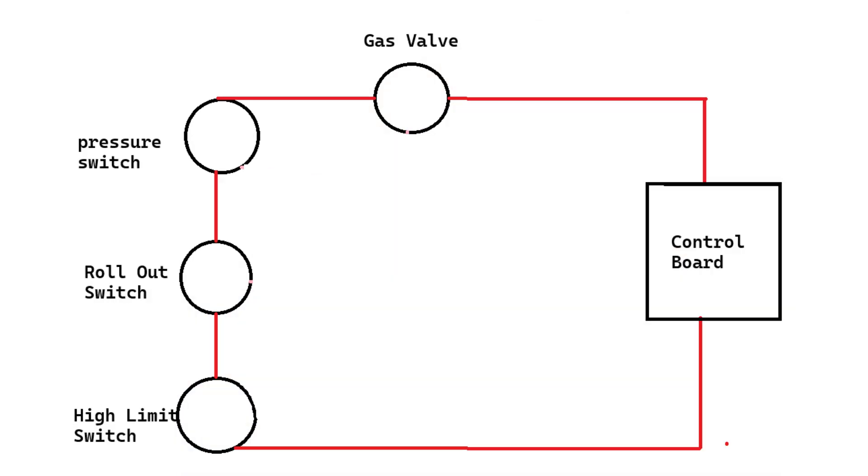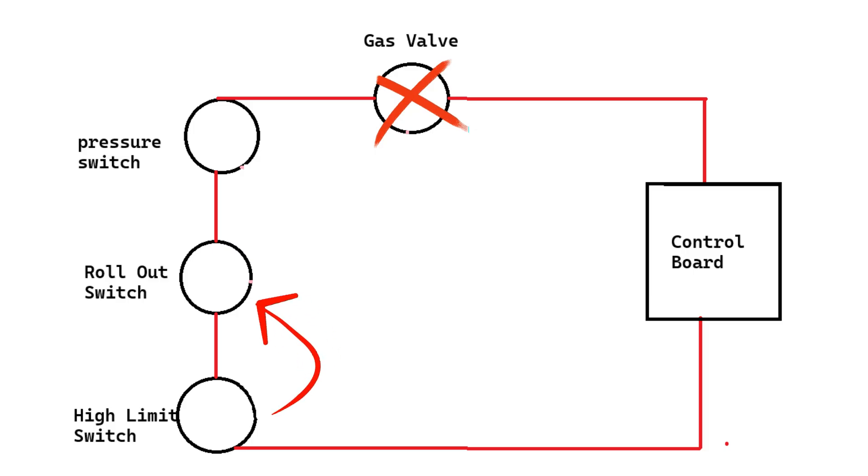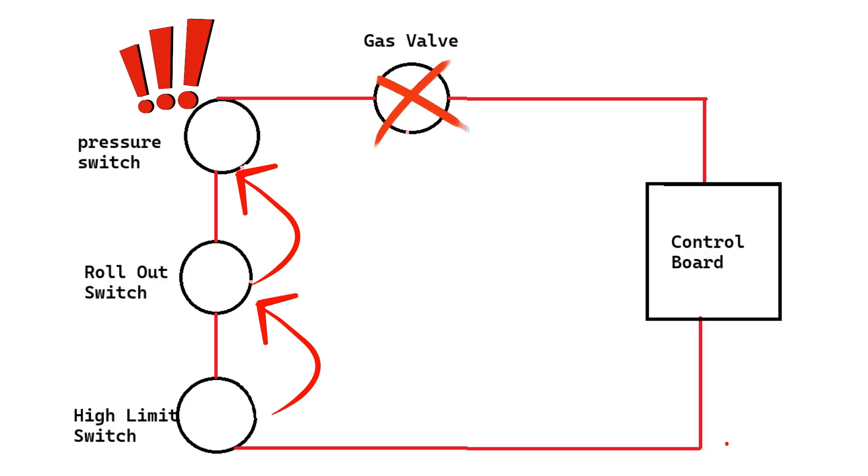Now a lot of older units, they don't have this set up. They can't tap into different parts of the circuit, and throw out an error code that specifically says where it's failing. So if you're not getting 24 volts to the gas valve, you have to manually hopscotch through the circuit one component at a time until you find out where the voltage is stopping.